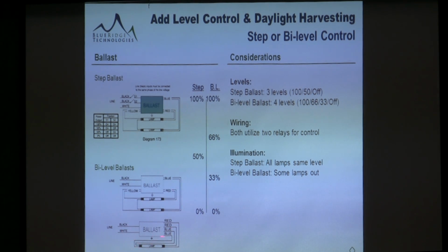So in a lot of cases, we've seen that. This control strategy has been around for years for daylight harvesting. It got implemented, I saw it a lot in K through 12 in schools. And of course, the first thing that happens is the teacher calls the maintenance guys and they say, well, okay, we'll come and fix it. And their idea of fixing it is basically bypassing. So they just paid for all this nice daylight harvesting equipment, and you've got a system that's been bypassed, because they didn't understand what was going on.